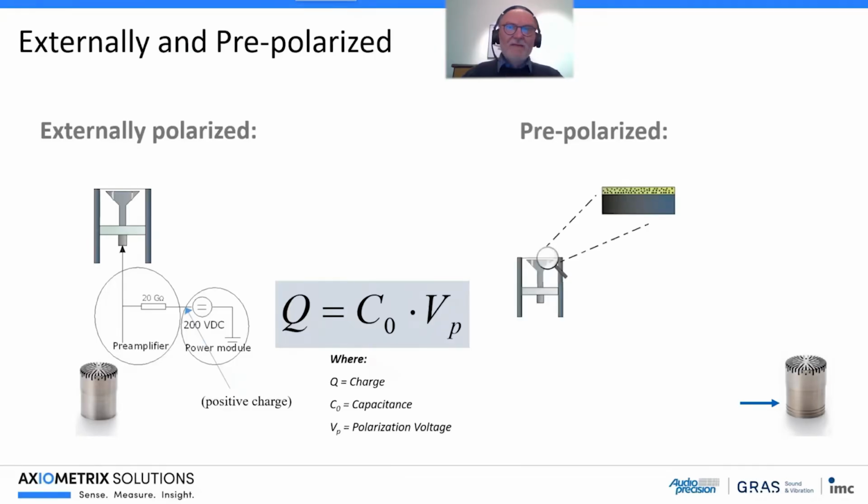The pre-polarized microphone is actually very similar, but on the backplate we do have a layer, and this layer has been charged with electrons, so they are negatively charged.